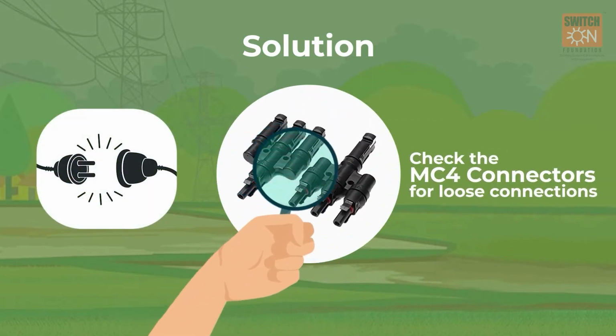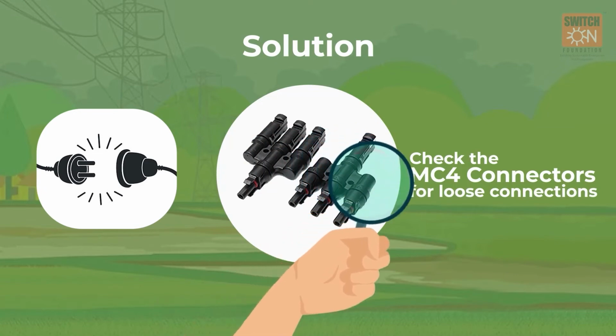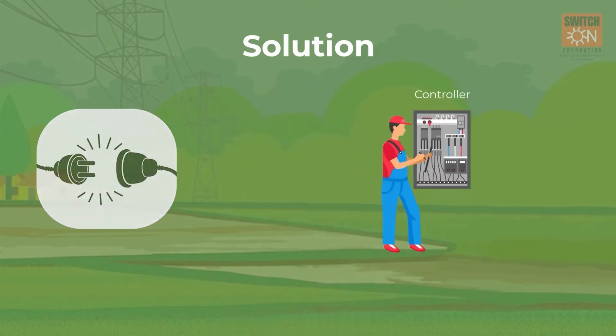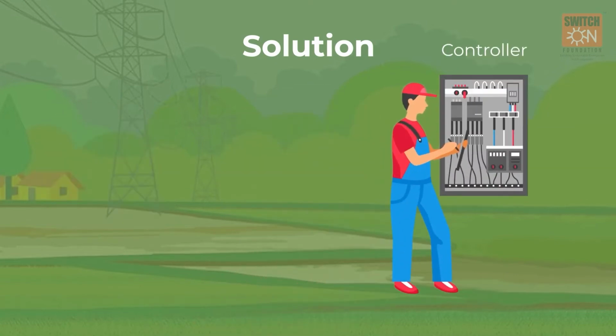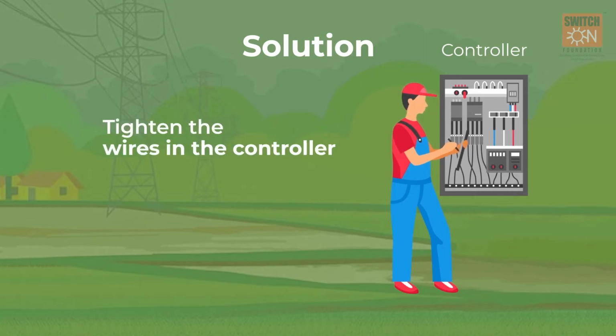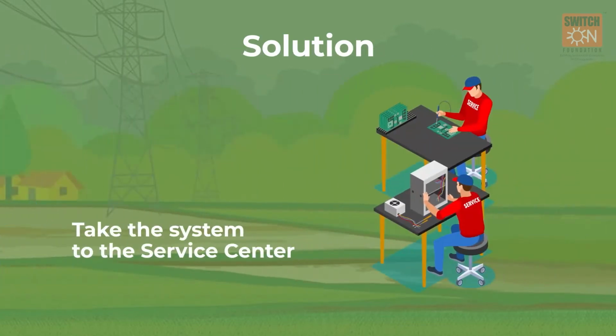Also, the MC4 connectors need to be checked for loose connections. In case the pump controller is out of order, the wires in the controller need to be tightened or reconnected if they have fallen out. If the controller still does not work, it has to be taken to the service center.